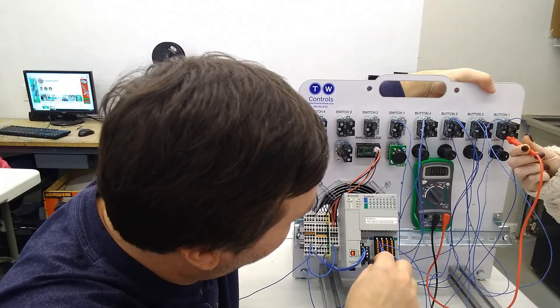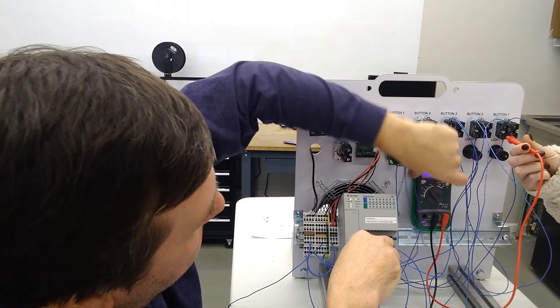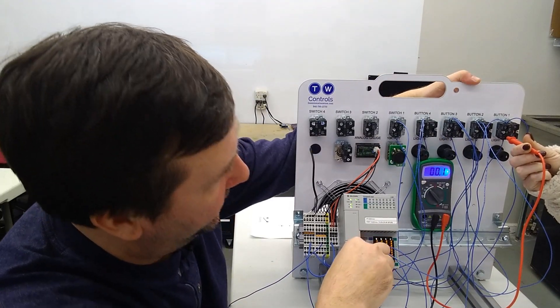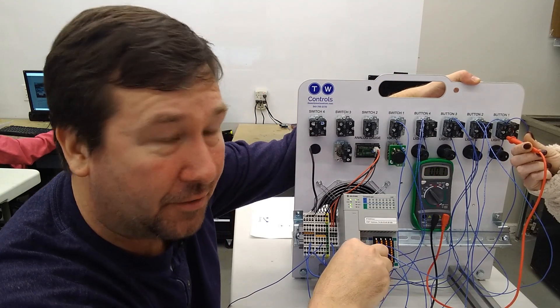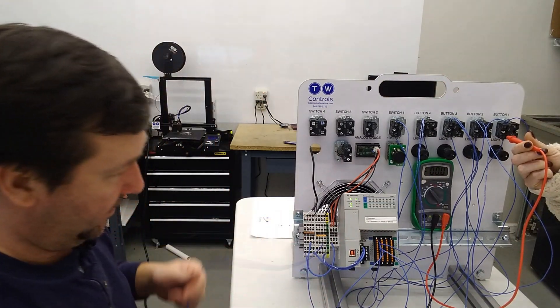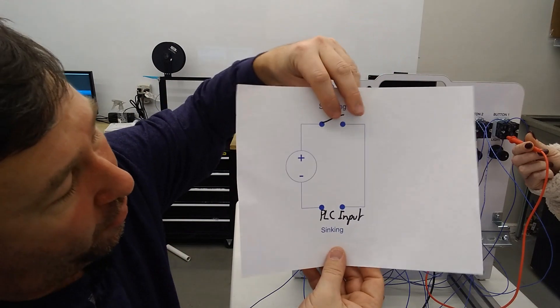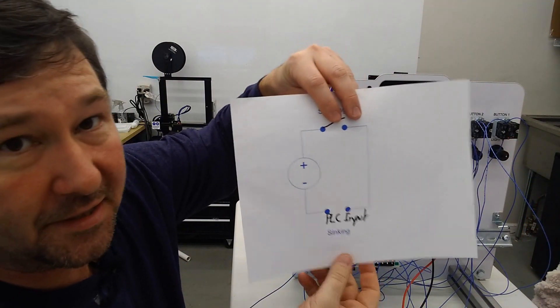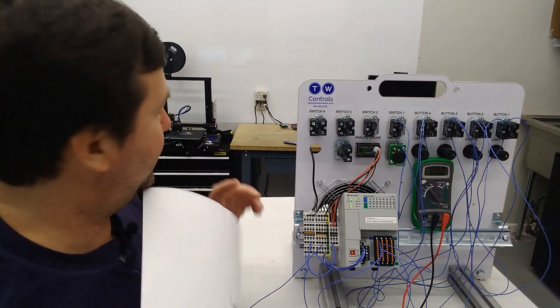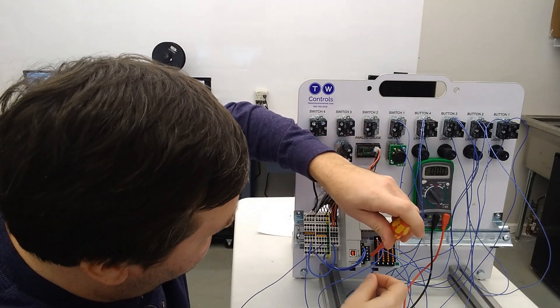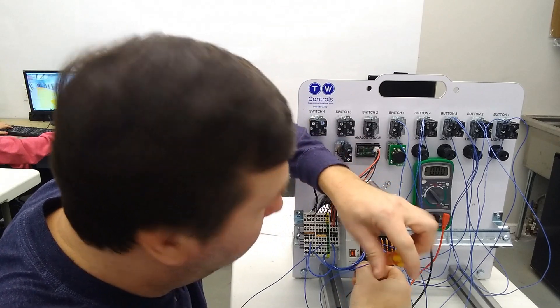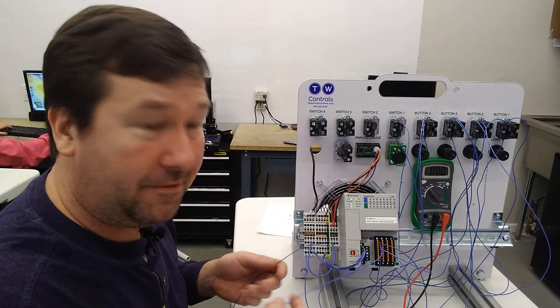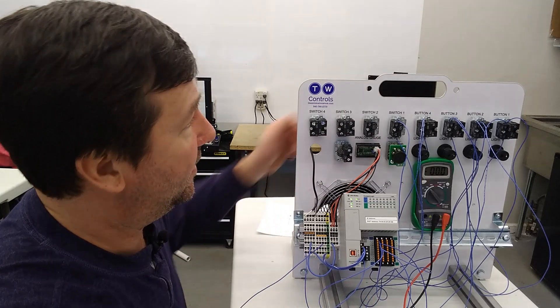I have to get my better half mode. I have to get Amber to come help me out on this. But if I check between FP minus and button one, I don't get anything. I get like 0.3 volts. So I don't have power across that PLC input. That is the important part is making sure that that last little bit of circuit is connected. Thank you, my lovely assistant. If you follow that part of the exercise, then make sure that you put your FP minus back on again, because as we play with these, it's really easy to forget to reconnect something.